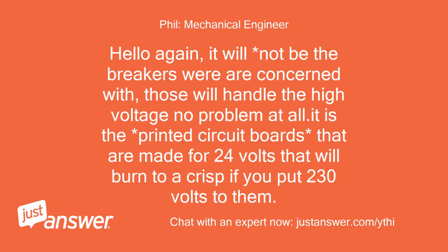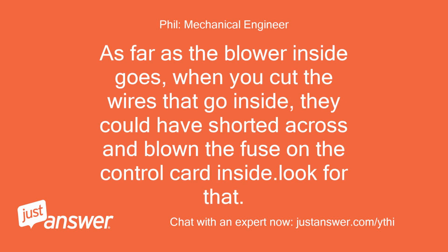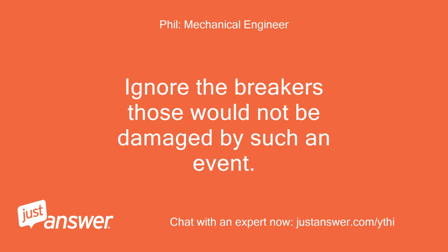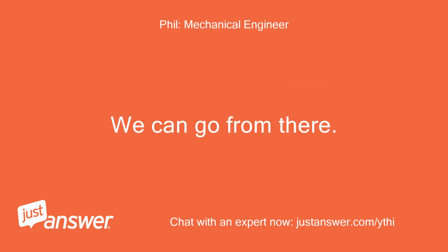Hello again. It will not be the breakers we are concerned with; those will handle the high voltage no problem at all. It is the printed circuit boards that are made for 24 volts that will burn to a crisp if you put 230 volts to them. As far as the blower inside goes, when you cut the wires that go inside, they could have shorted across and blown the fuse on the control card inside. Look for that. Ignore the breakers, those would not be damaged by such an event. We can go from there.